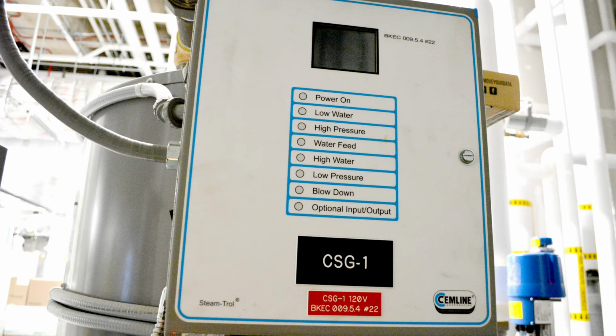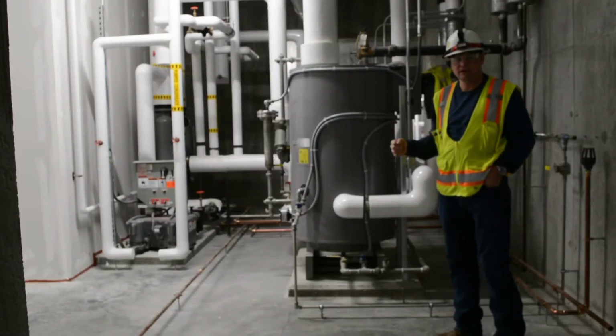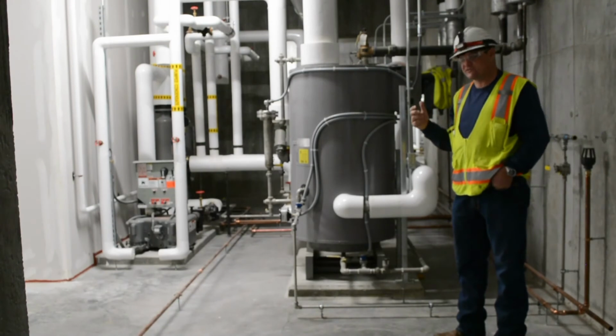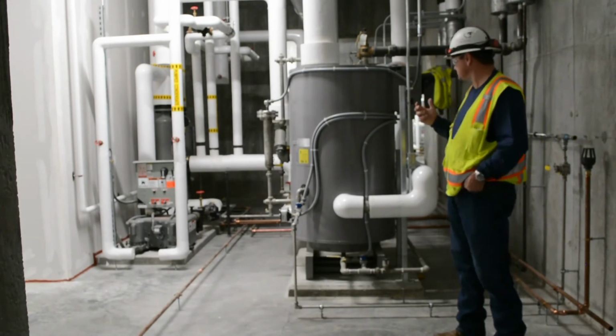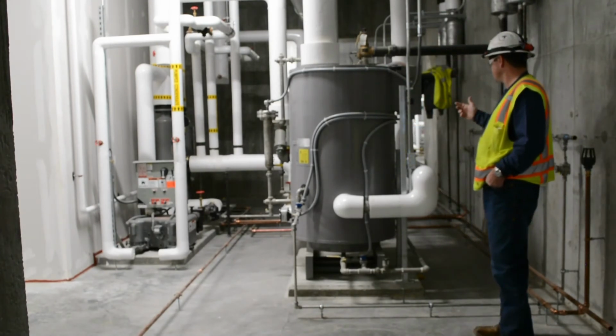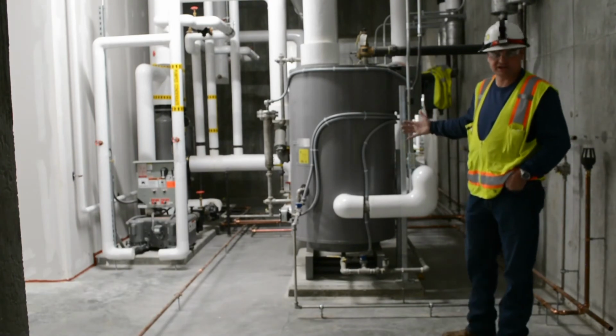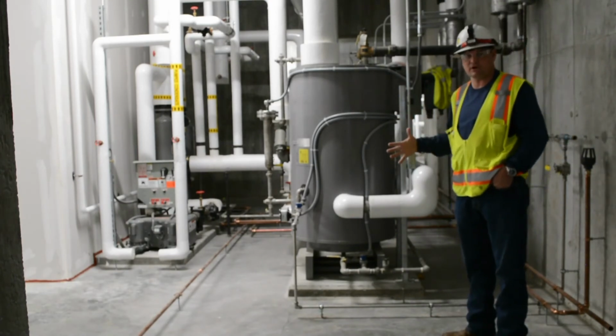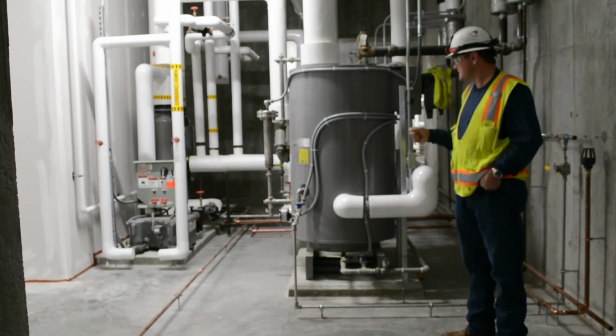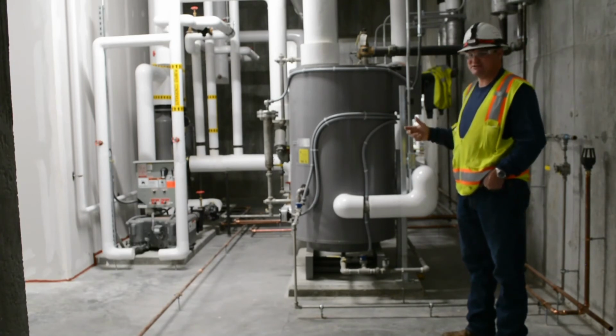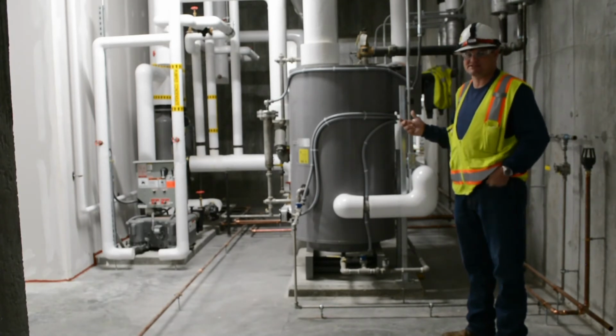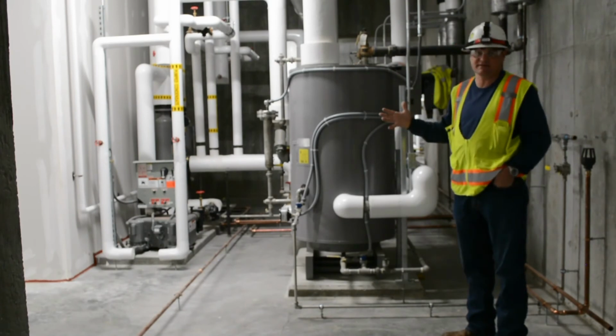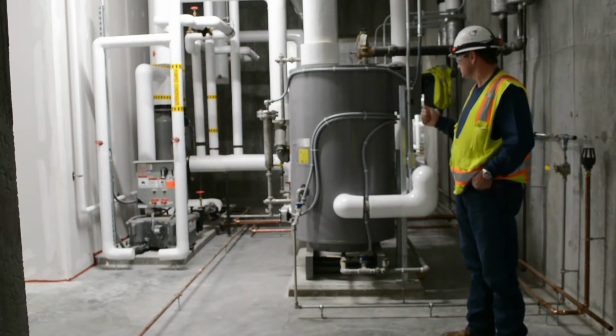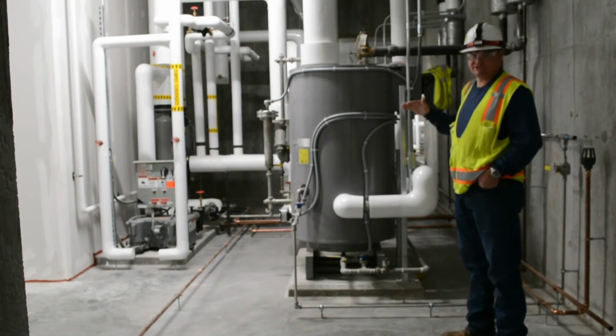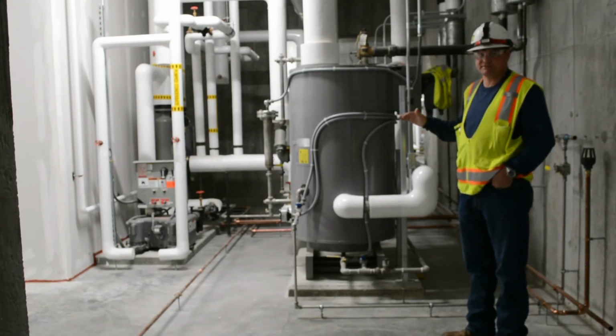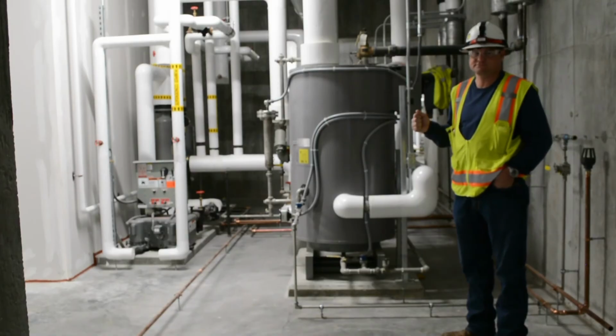They do automatically operate. They'll automatically blow down. There's really no routine maintenance other than annually you'll want to inspect the heat exchanger where the steam to hot water to steam converter is. In the event you're not making the proper amount of steam, then you'll definitely want to inspect that as needed. All the fill and drain controls are all internal to this machine and is done automatically as well.